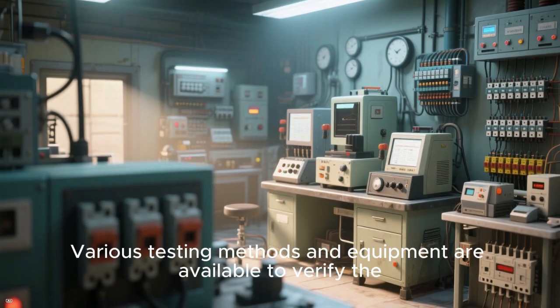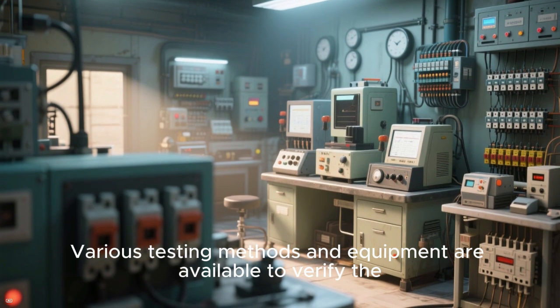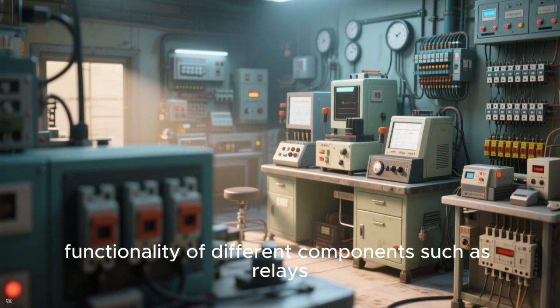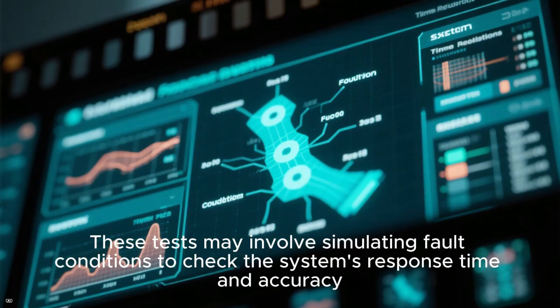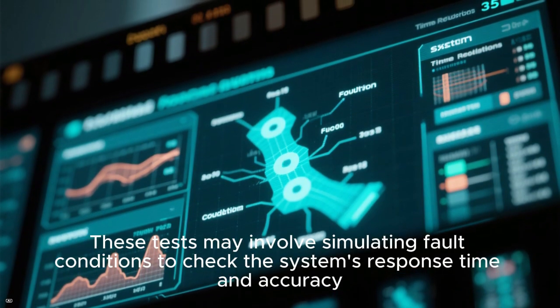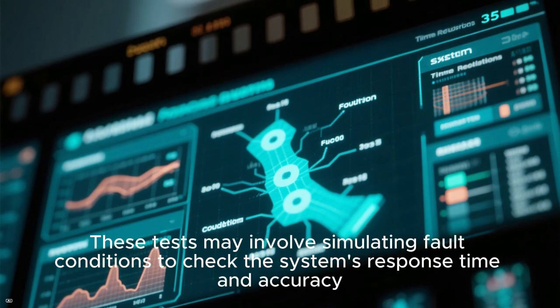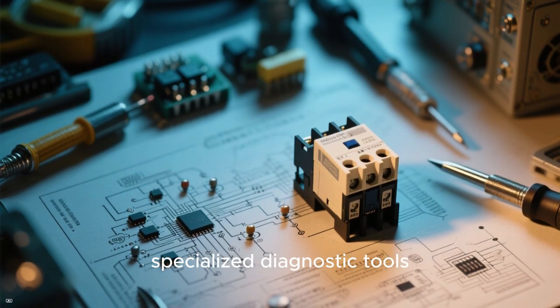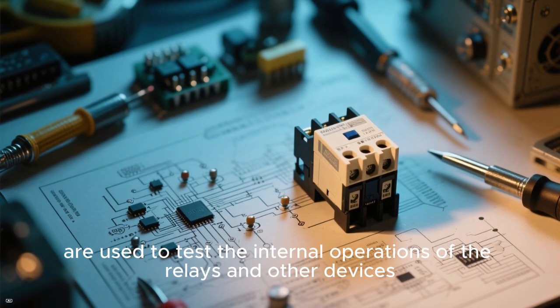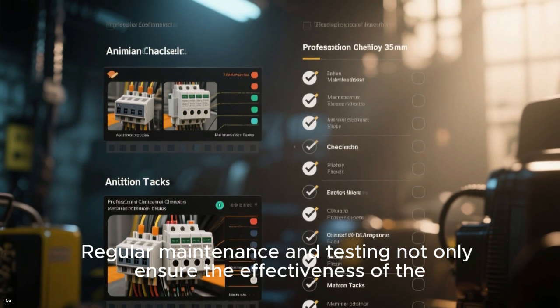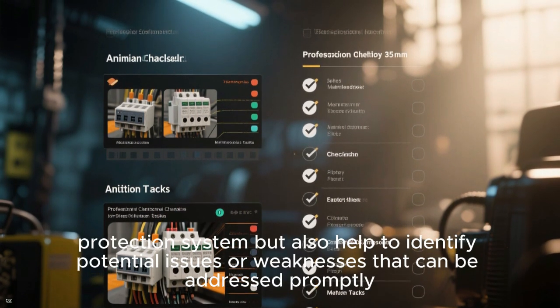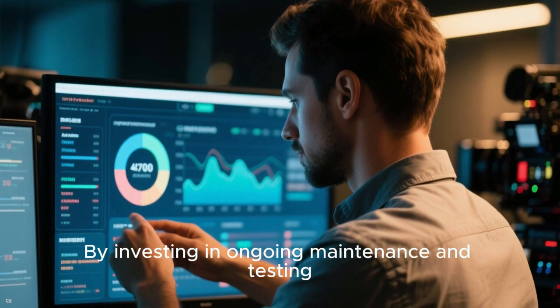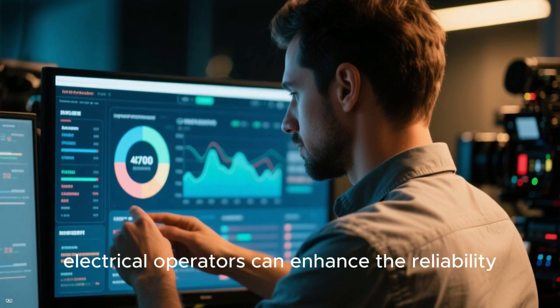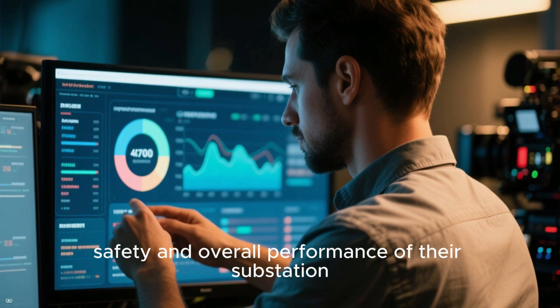Various testing methods and equipment are available to verify the functionality of different components, such as relays, circuit breakers, and transformers. These tests may involve simulating fault conditions to check the system's response time and accuracy. Additionally, specialized diagnostic tools are used to test the internal operations of the relays and other devices. Regular maintenance and testing not only ensure the effectiveness of the protection system, but also help to identify potential issues or weaknesses that can be addressed promptly. By investing in ongoing maintenance and testing, electrical operators can enhance the reliability, safety, and overall performance of their substation protection relaying systems.